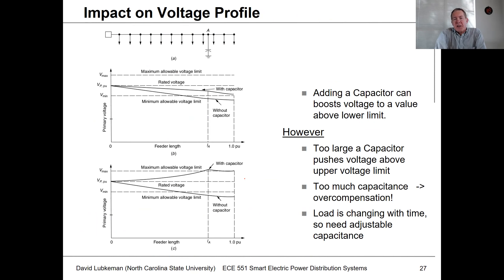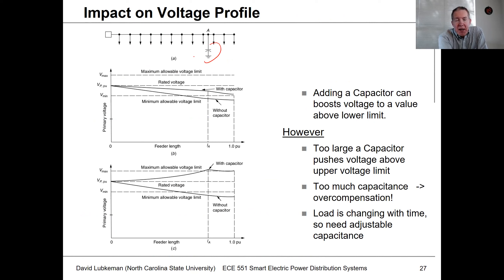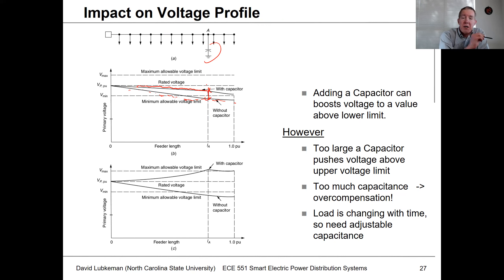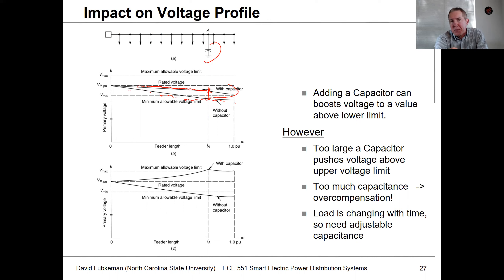If you look at the impact on the voltage profile on a distribution feeder, suppose we put a capacitor toward the end of the circuit. Without the capacitor, you get a curve where the voltage is dropping until we get to the end of the feeder, and perhaps it drops below the minimum acceptable threshold used for planning purposes. To fix this, we put a capacitor in at that point. This has the impact of changing the slope on the curve — we get a voltage rise up to where that capacitor is located, and it changes the slope. We're basically modifying the profile. Once we get past the capacitor, we have the normal voltage drop as before.